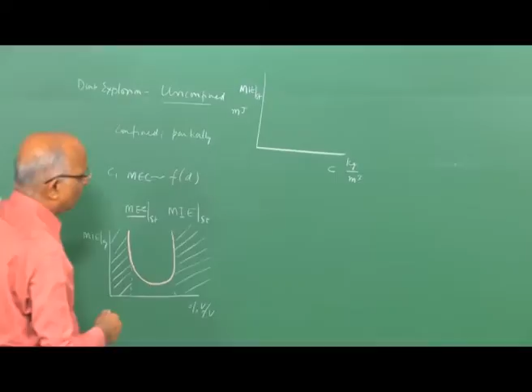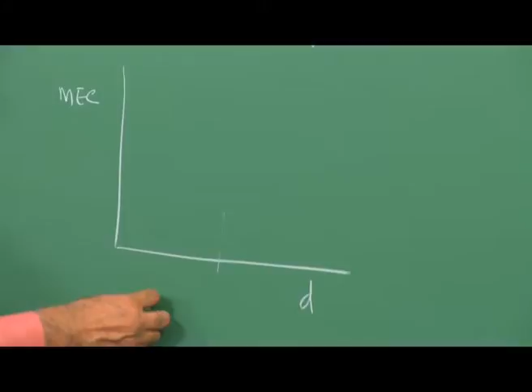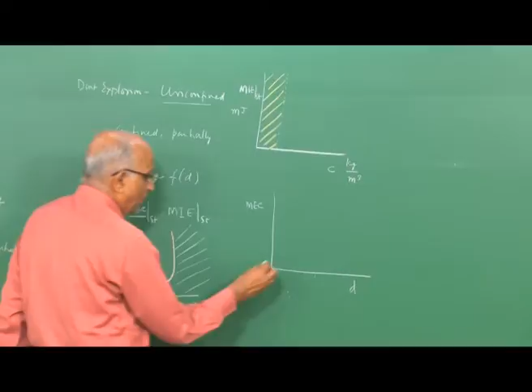How did we come to this? We said, well, I plot the diameter of the dust particles over here. I plot over here the minimum explosive concentration, MEC, for the dust mixture, and what did we find? Well, if the diameter is quite small, well, I have some minimum concentration is required such that flammable vapor air mixture can form just at the limits of flammability, and therefore I require some minimum explosive concentration when the diameter is typically less than around 100 micron or so.